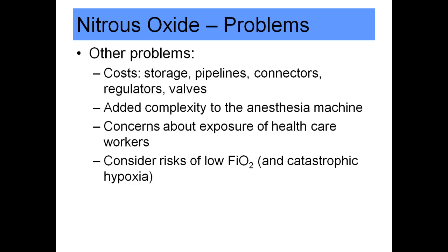There are other issues about nitrous oxide. There are a lot of costs due to storage, pipelines, and connectors. The anesthesia machine is more complicated because we have to prevent administration of a hypoxic mixture or a gas line crossover. There's data about exposure of healthcare workers — even nurses in the PACU have been shown to be breathing elevated levels of nitrous oxide above OSHA guidelines, just from patients exhaling it after being brought from the operating room. There have been studies about increased potential risks of miscarriage in dental assistants, and we always worry about potentially giving somebody a low FiO2 by using high concentrations of nitrous oxide.